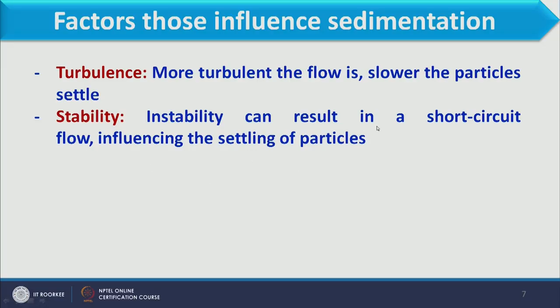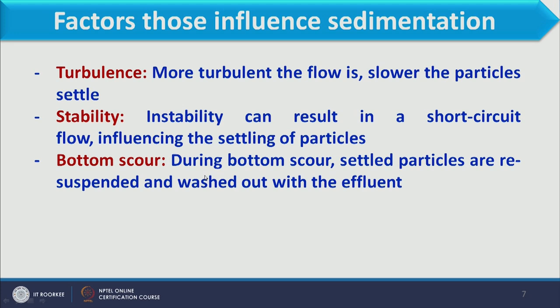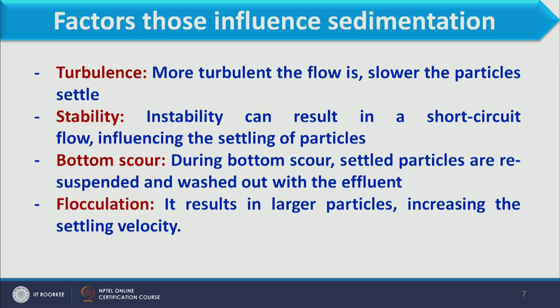Instability can result in short-circuit flow that influences the settling of particles, so stability in the process is needed. Bottom scour is another factor — during bottom scour, settled particles are re-suspended and washed out with the effluent. Flocculation results in larger particles and thus increases the settling velocity, as discussed for potable water treatment systems.